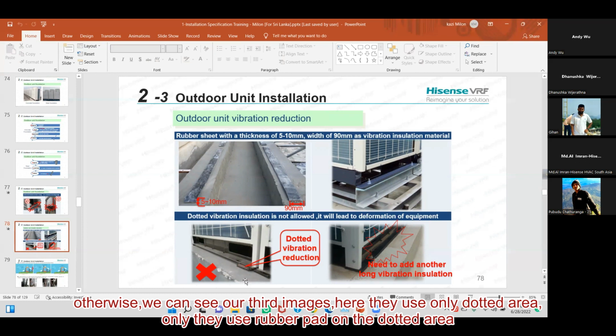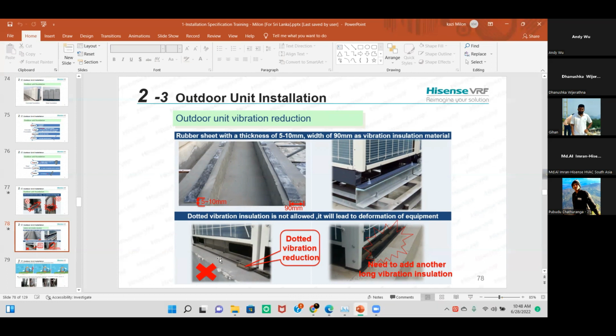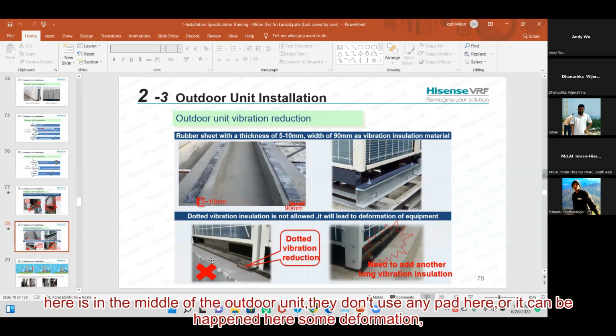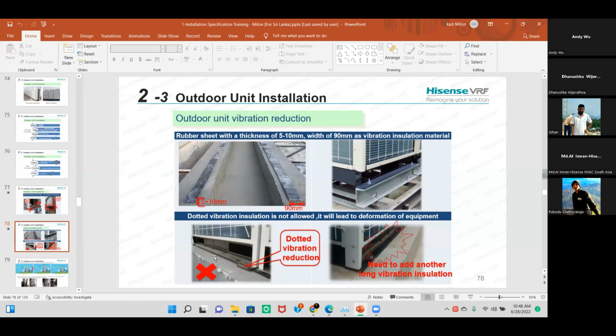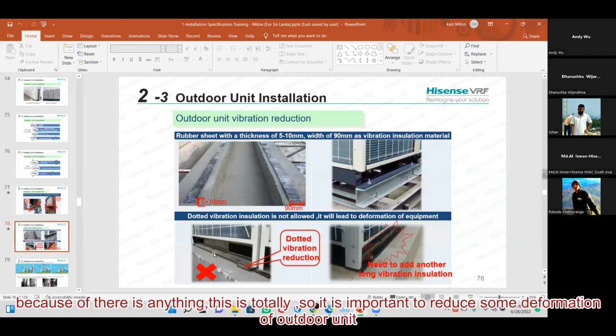Otherwise, we can see in our third image, here they use the rubber pad only in the bolt area. In the middle of the outdoor unit, they don't use any rubber pad. Some deformation can happen here because this is totally empty. So it is important to reduce deformation of the outdoor unit body.